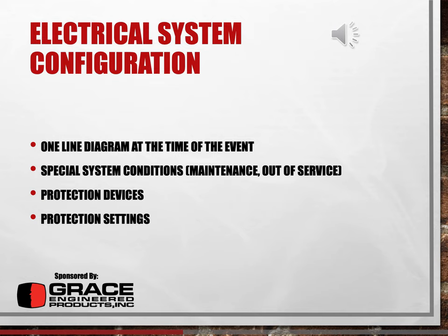One of those things you're going to want is a one-line diagram of the electrical system at the time of the event. Now, that may be different from the one-line diagram you have in-house. Maybe your one-line diagram is not updated, maybe it's out of date. Maybe maintenance was going on at the time of the accident and your system was operating in a way that's normally not operated. So you'd want to create that one-line. And if you have an existing one-line, you might want to modify it and write notes on how the system was at the time of the accident for documentation. And make sure you only write factual information. Do not write any opinions or thoughts on what you think caused the accident. It's got to be factual.